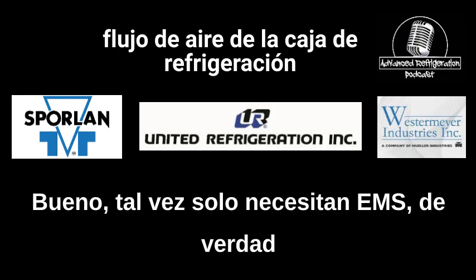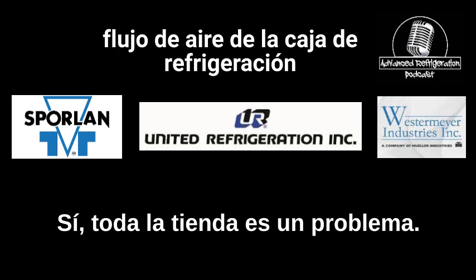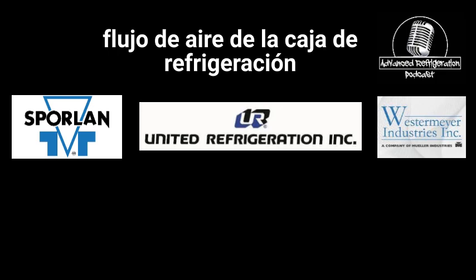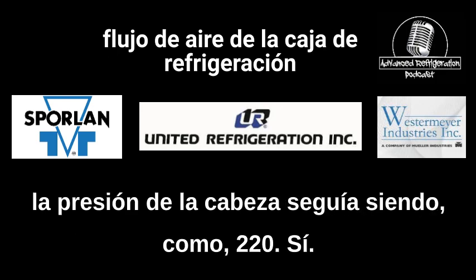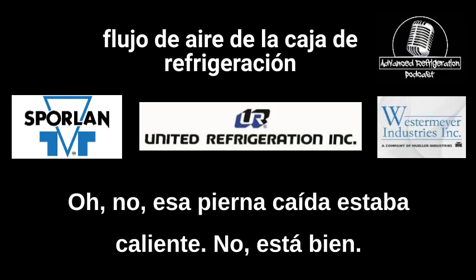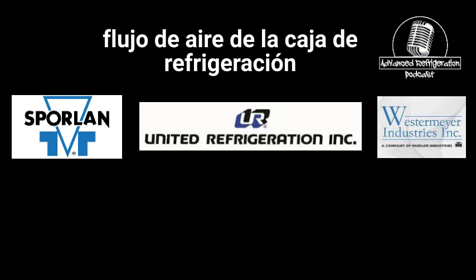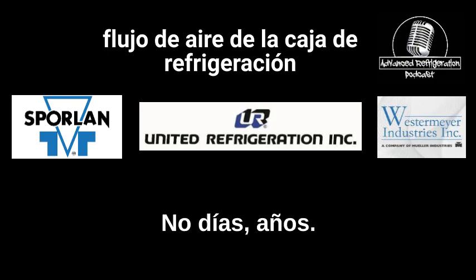Well, maybe they just need EMS, really good EMS, to make sure it catches all the issues because everything's so old. Maybe. Yeah, like the whole store is an issue. Like the HVAC. Put it this way: the sprinklers were on yesterday. It was 54 degrees outside, and the head pressure was still like 220. Yeah, but there could be copious amounts of non-condensables in there too. Oh no, that drop leg was warm. Yeah, it was warm. Those condensers have seen better years, not days, years.